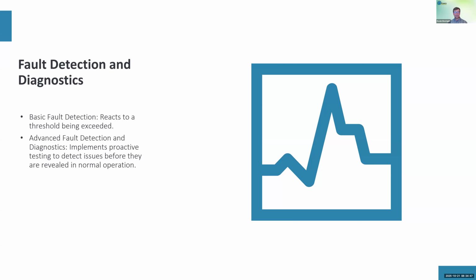Slightly more advanced than that would be creating a rules-based fault detection diagnostic system, where something along the lines of you look at air handler fan speeds, and if the fans are at 100% and our static pressure set point is still not being met, you can trigger an alarm that indicates we have a problem here with the fans or the motors, possible blockage in the duct, maybe a problem with the set point itself.